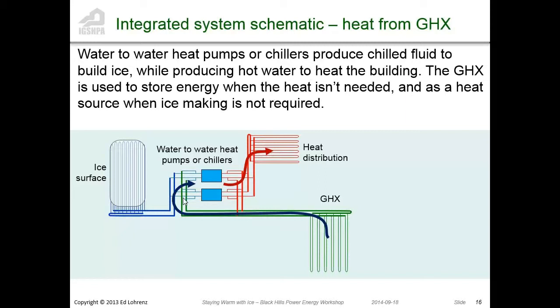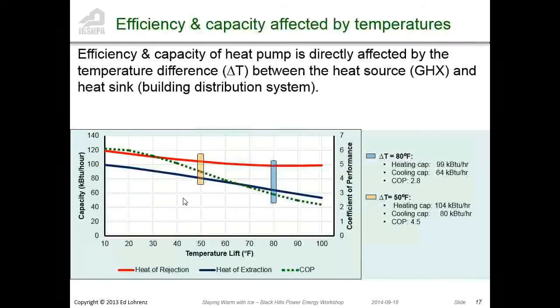And again, the efficiency of the heat pump, you've got to be aware of what's happening with that. The COP changes the bigger the temperature lift is. So if you're heating the building with 80-degree water to a radiant floor heating system, that's going to be a lot more efficient than trying to heat that building with 110 or 120-degree air going to air handlers.